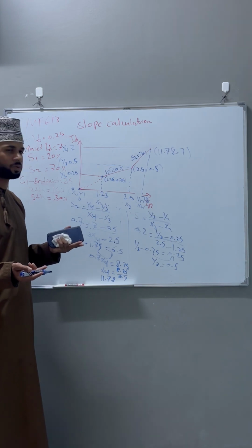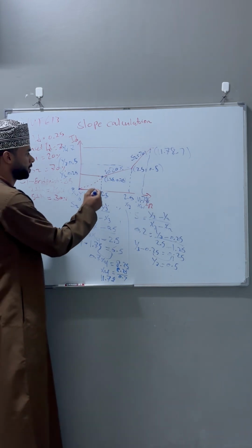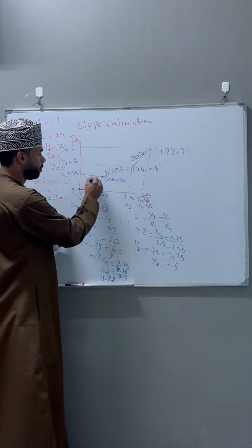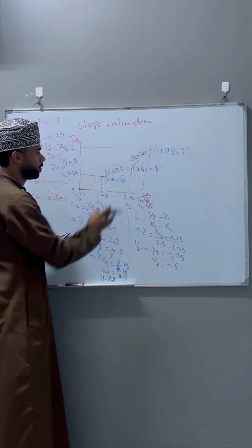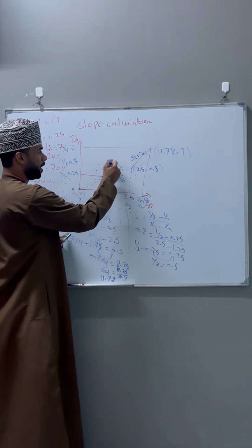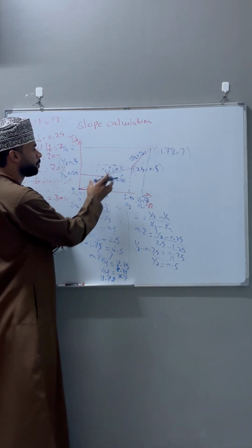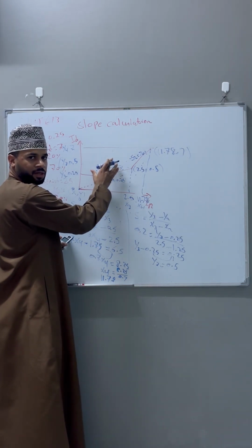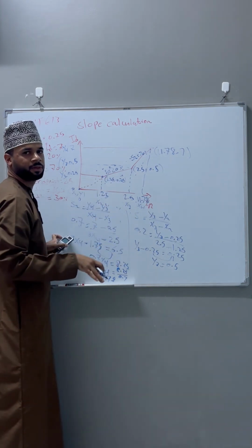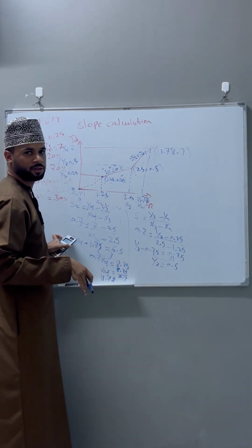Okay, then on the slope we also need to do testing. For example, we need to do the shot test. As you know, in the shot test I will give some points below the slope, and some points above the slope. And any point above the slope means I will get what? Trip. And a point below the slope should not trip.